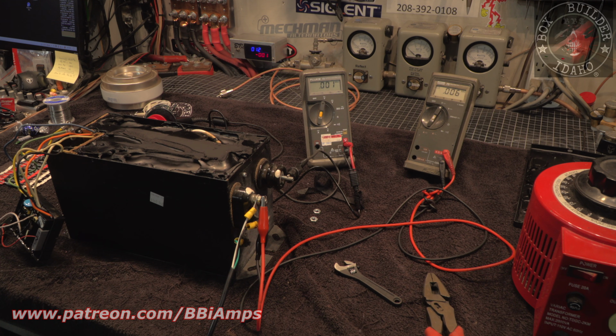14,500 times 1.145. So we're going to see approximately 16,000-ish volts, 16,600-ish. I doubt we'll get there because diodes and wire loss and reasons and stuff. Anyhow, so we should be able to achieve a 6,000 volt DC rectifier with this DC transformer power supply at around 0.5 of an amp, which is a lot, but it's definitely enough to high pot with.